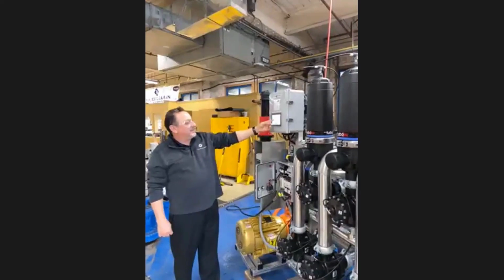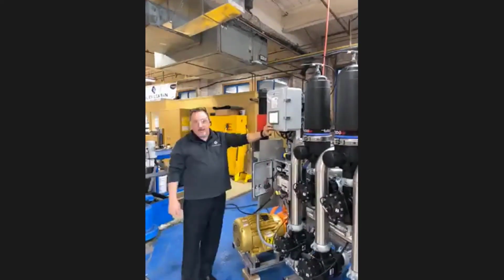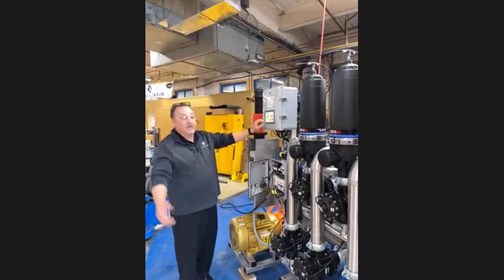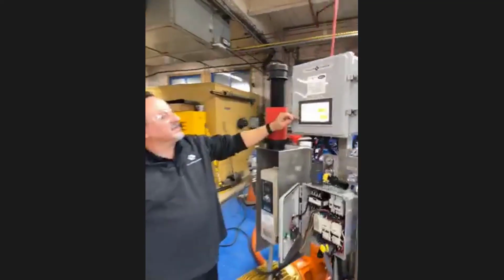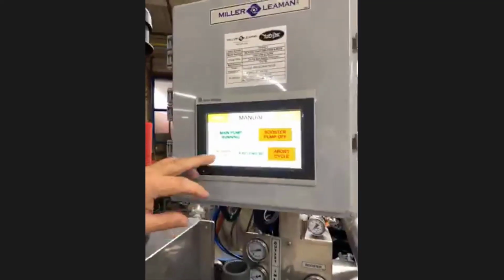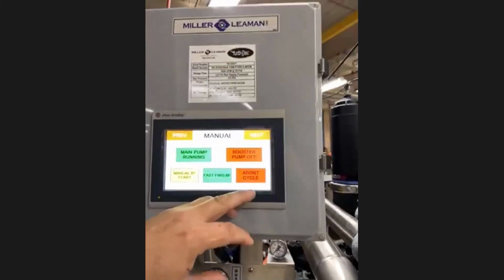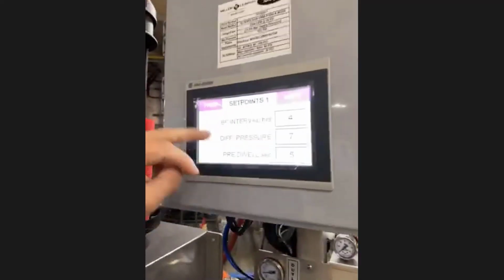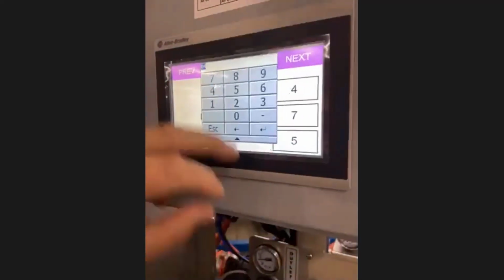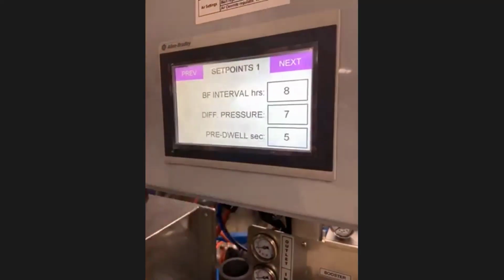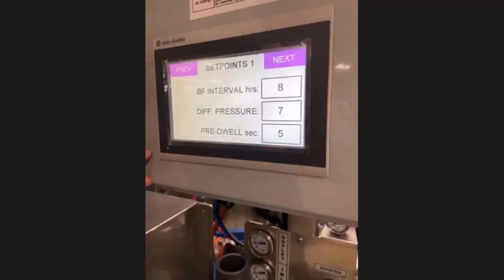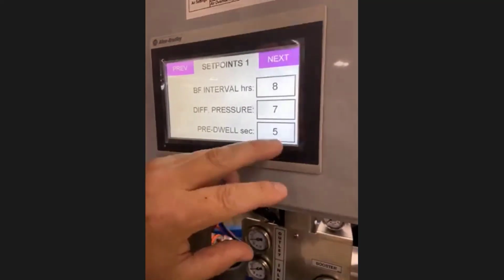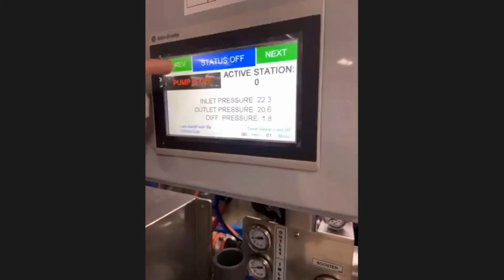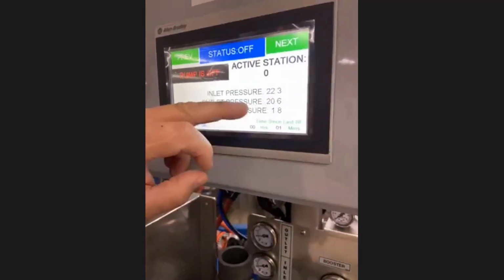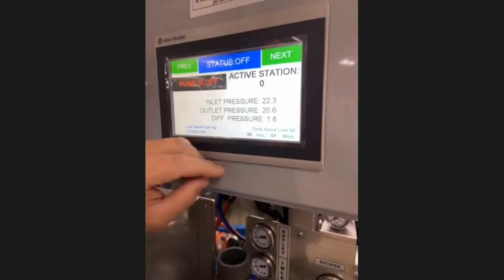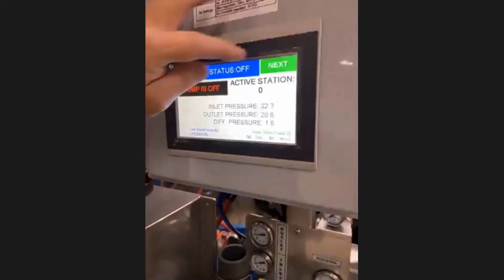But with the Allen Bradley, you can see how nice it is. It gives you basically the screen itself. I'm going to step over here, Sarah, if you can see that. It'll tell you the main pump running, the booster pump is off, manual start, fast forward, backflush, abort cycle. It'll give you the backflush intervals in hours. If you want to change that to 8, it's very simple to change. Differential pressure at 7 psi. The pre-dwell is at 5, and we also have transducers monitoring the system right here. Inlet pressure 22, outlet pressure 20, differential 1.8.